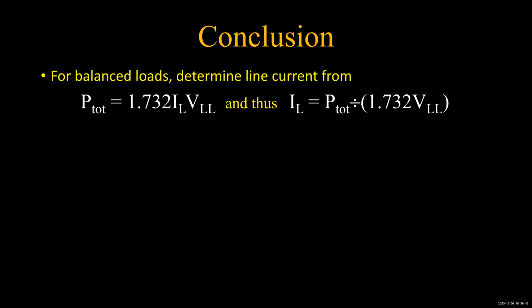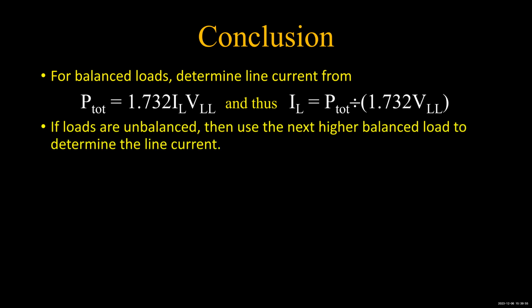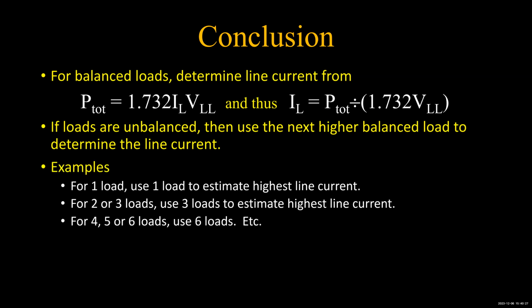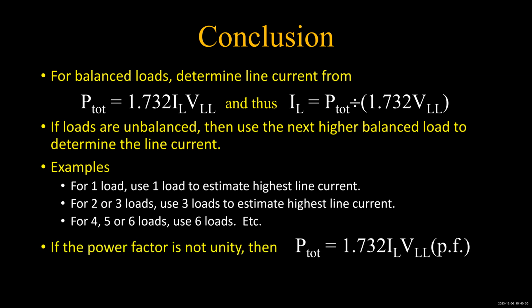So bottom line, the line current is the total power being delivered divided by 1.732 times line voltage, if you've got a balanced collection of chargers. And if they're unbalanced, you can still do a good conservative estimate by saying, if I've got 4, I'll simply consider the line currents to be what they would be with 6. And if I've got 7, then I'm going to have to use 9. And then that still gives you a reasonable, conservative calculation of the line currents. So if you have 7, you might as well put 2 more in because it doesn't change it. Okay. So there's the story there.